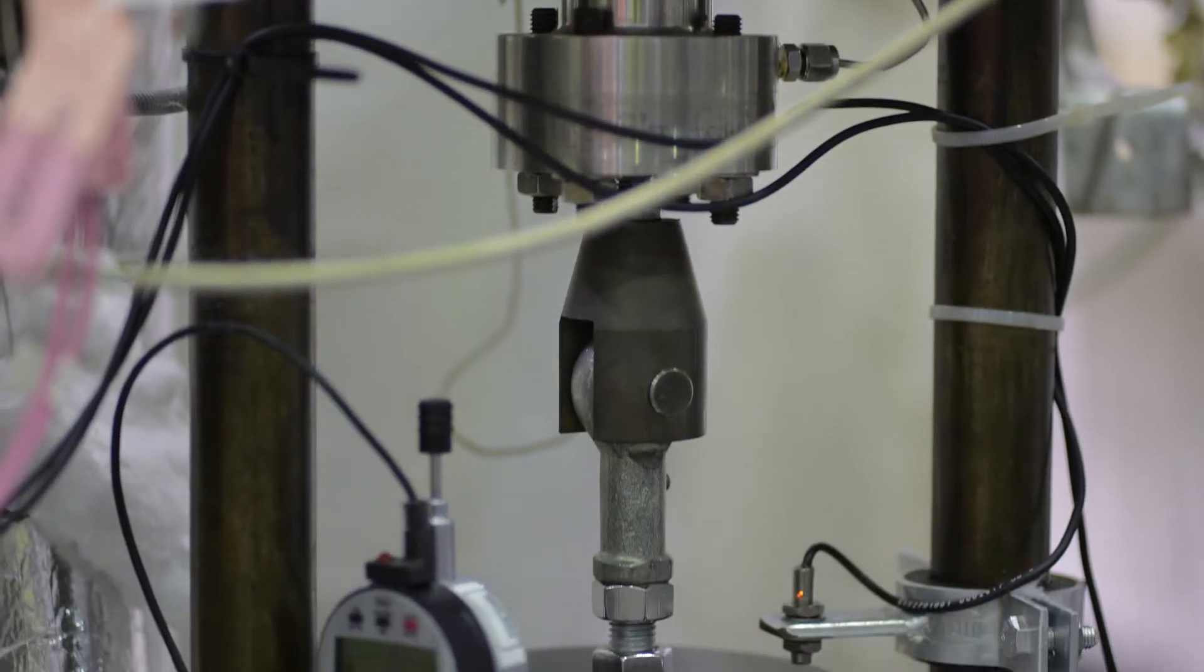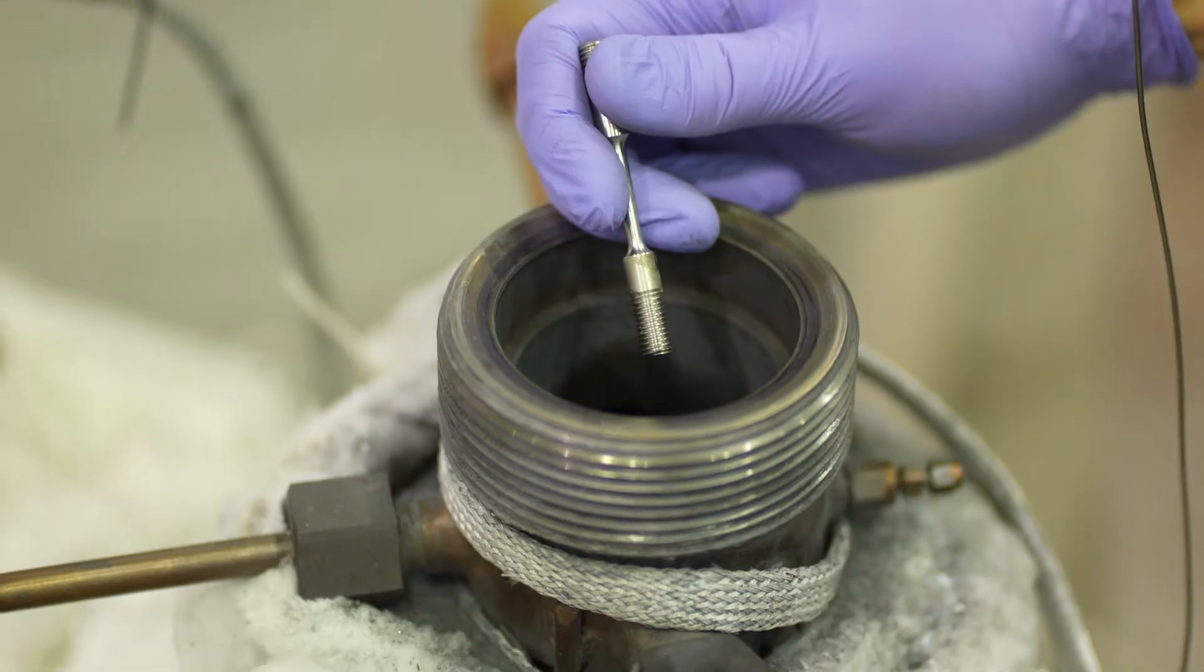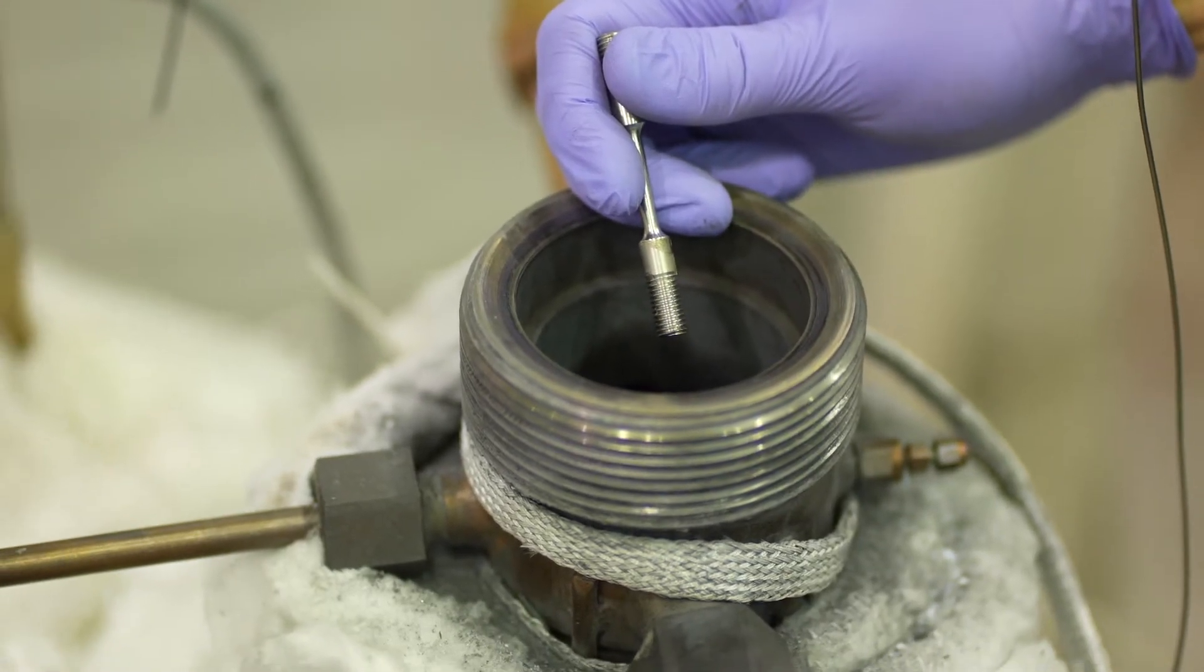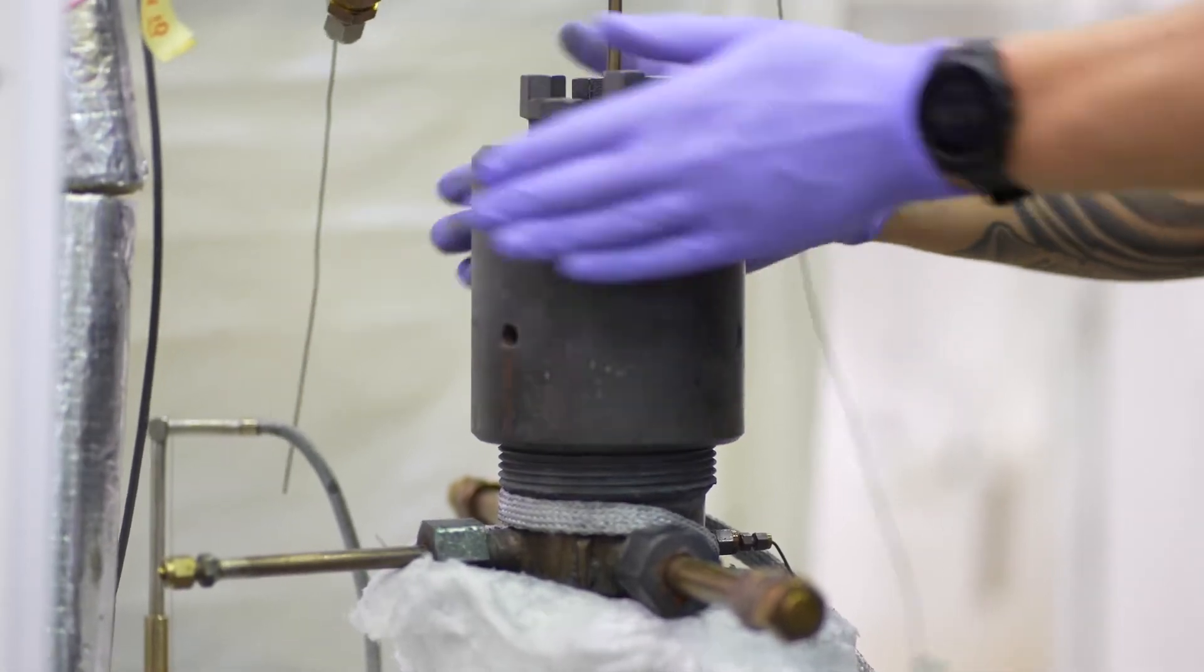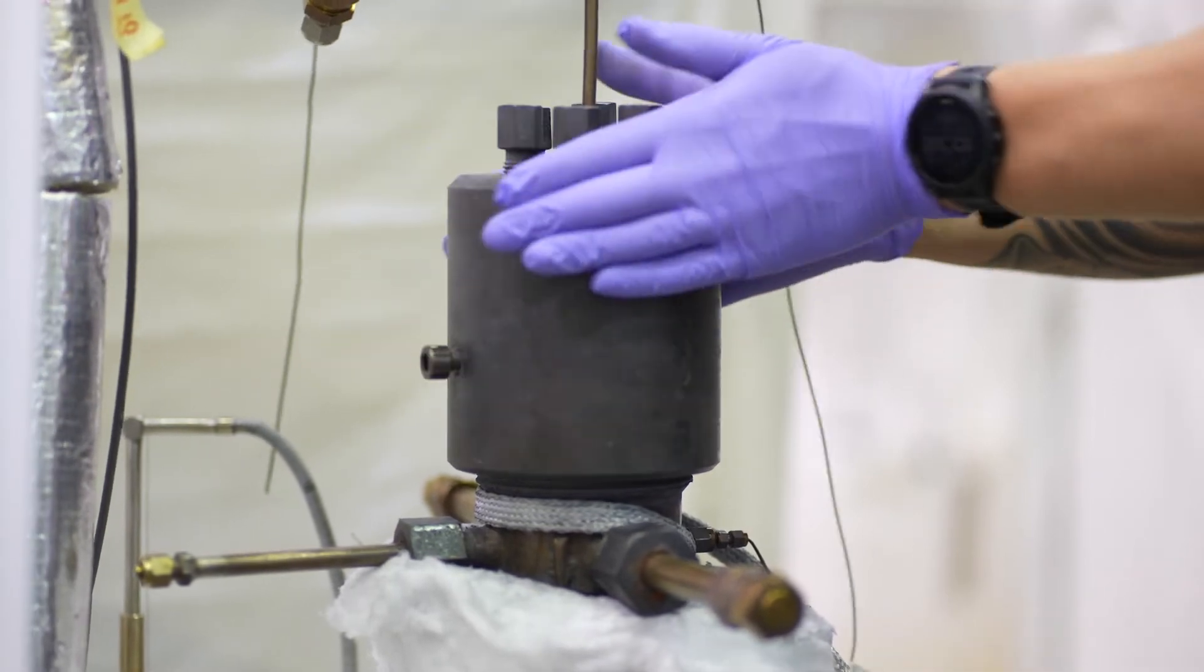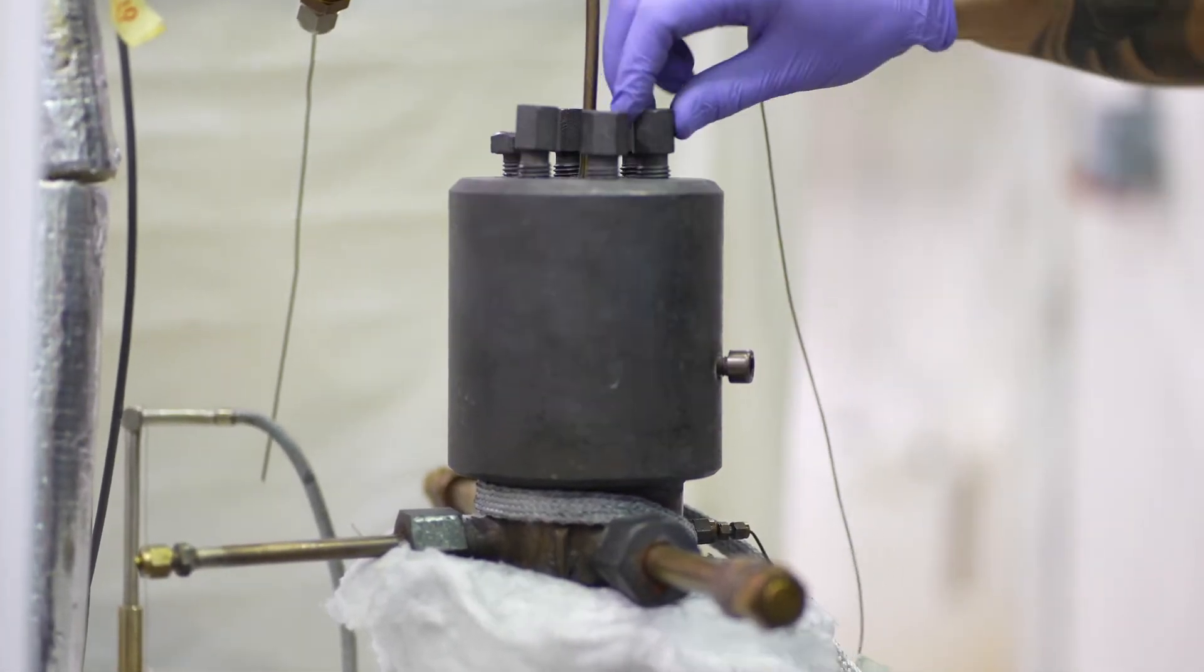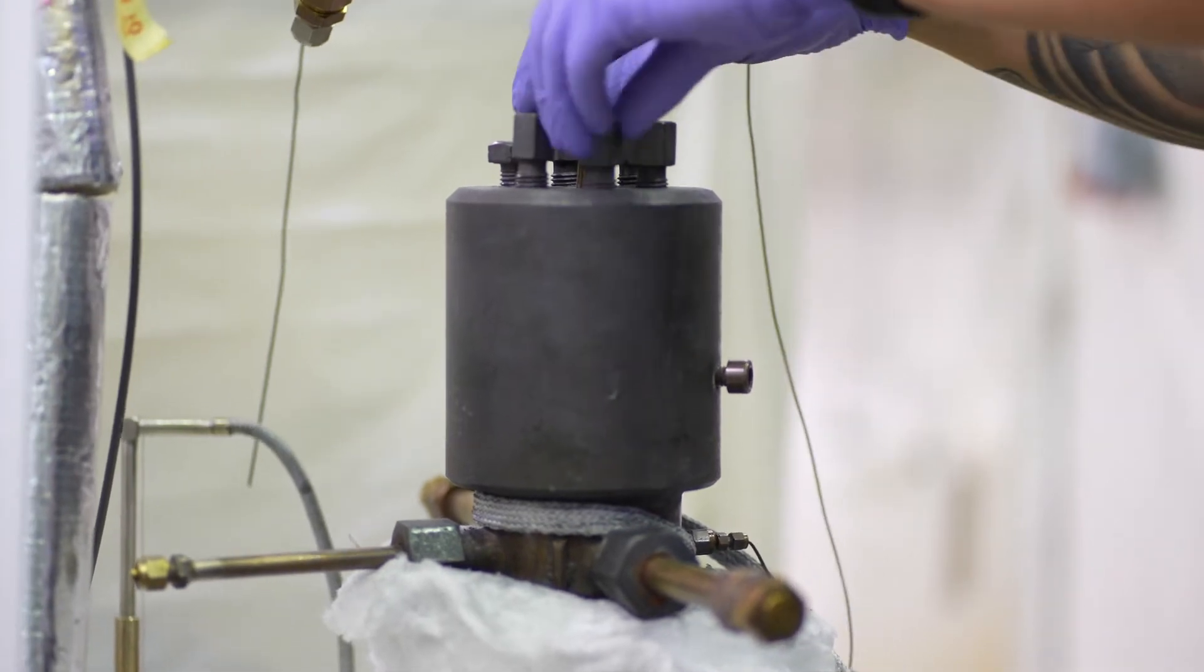The laboratory is equipped with test systems for crack initiation testing in simulated LWR environments. Advanced testing approaches where crack initiation is monitored by DCPD, as well as more basic tests involving exposure of large numbers of constant displacement specimens like reversed U-bend O-rings or slow strain rate testing, are possible.